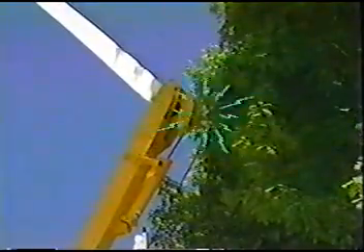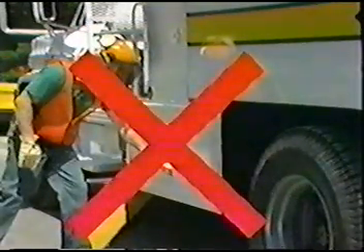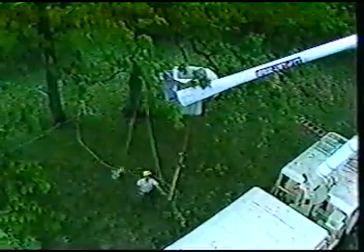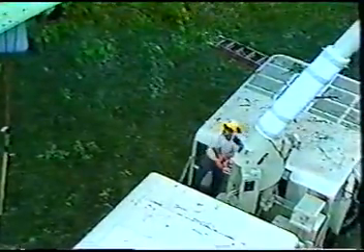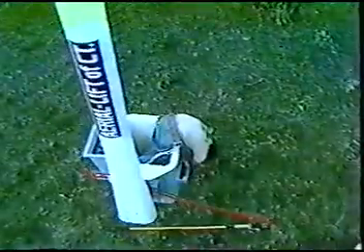Ground personnel are prohibited from touching an aerial lift device or any operating piece of equipment attached to it if the boom is in contact with the conductors, unless the operator moves the boom into a safe position and so notifies the ground worker. In the event that there is an emergency aloft and a person must get onto a piece of equipment to perform a rescue, contact with energized lines must first be broken, if such contact exists. If a fully insulated aerial device is involved, you can attempt to break contact by use of the lower controls. Proper procedures are described in aerial rescue training.